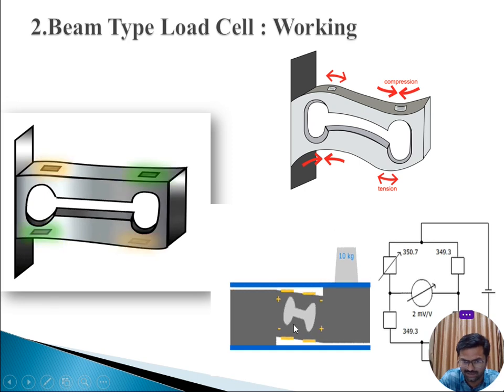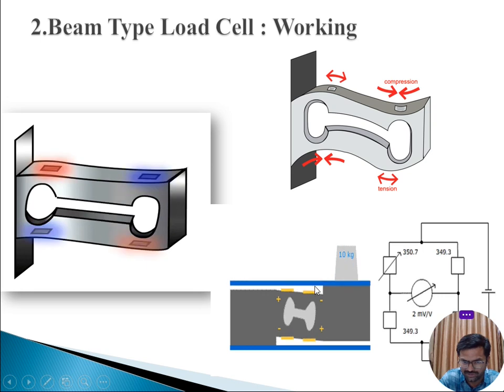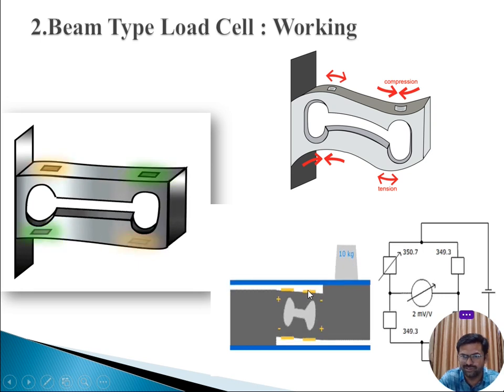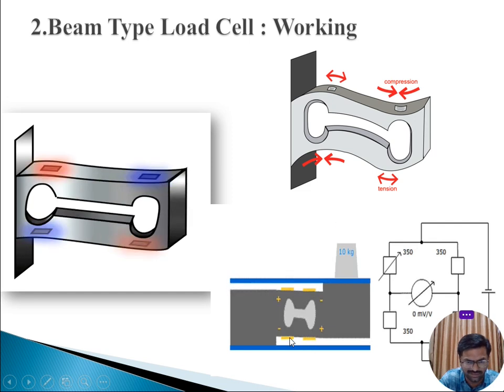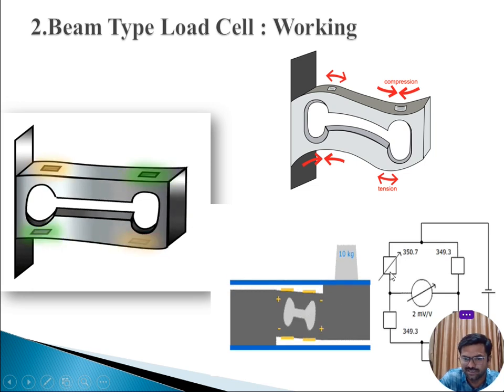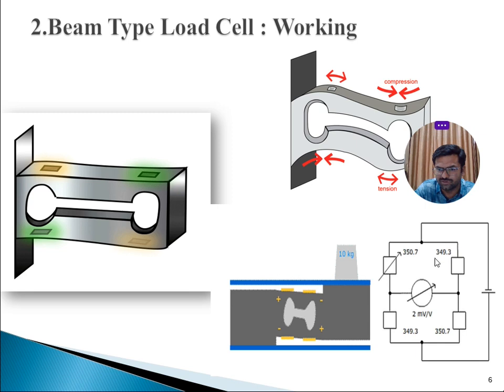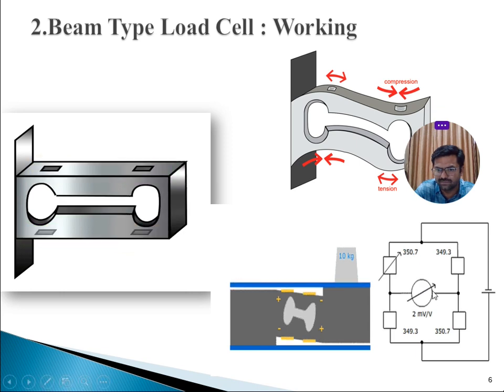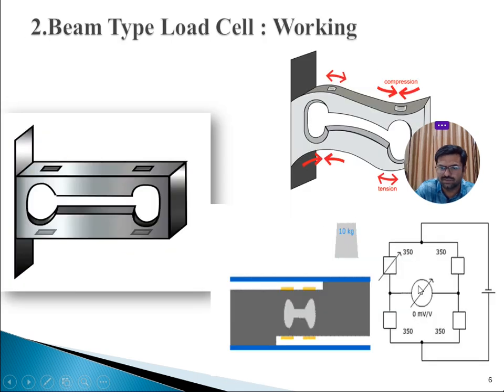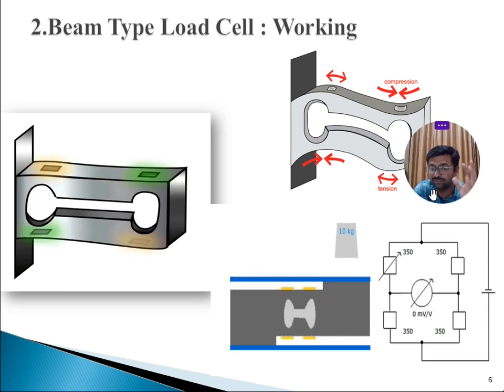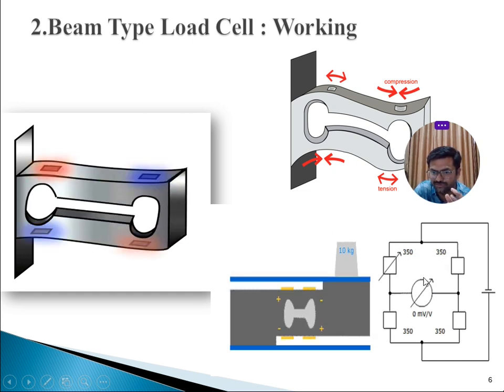The yellow-colored elements in the diagram are the strain gauges. After applying pressure, one gauge experiences compression, another tension, another compression, and the last tension. This results in a change in resistance — you can observe that previously all resistances were 350 ohms, but after applying pressure they change to values like 349 or 350.7 ohms.